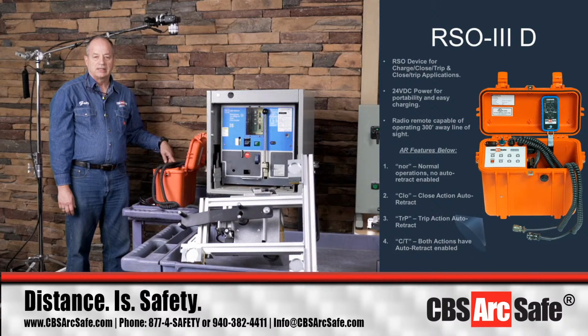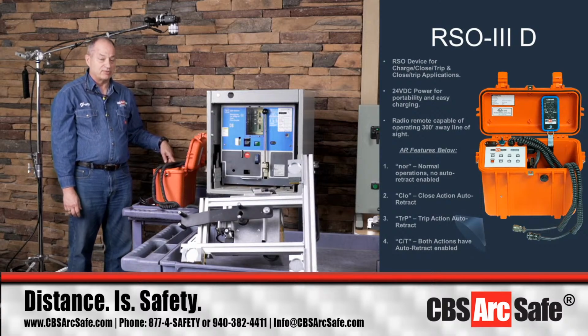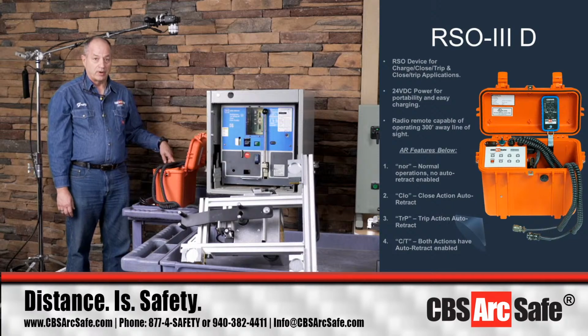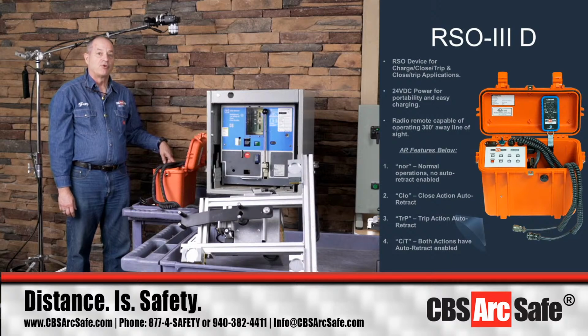What we have seen, I haven't seen it that much domestically, just a couple of times. I've seen it more internationally, where somebody's got a worn charging mechanism and they get to the bottom of the last charging stroke and all of a sudden the breaker closes by itself. That is not normal behavior, and the real answer you need there is breaker maintenance.